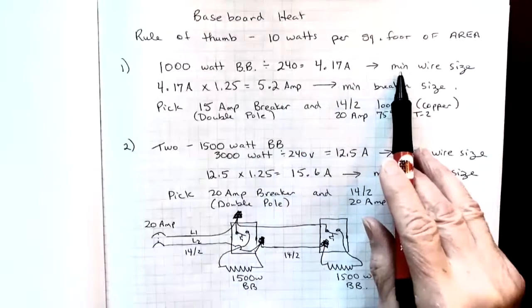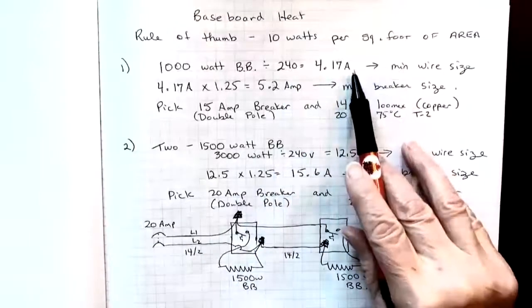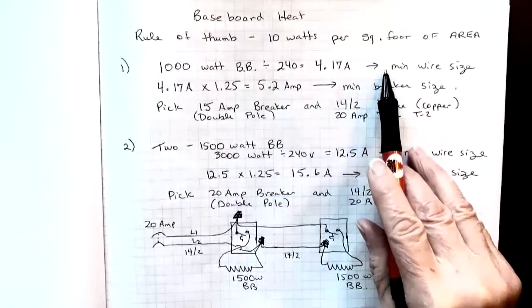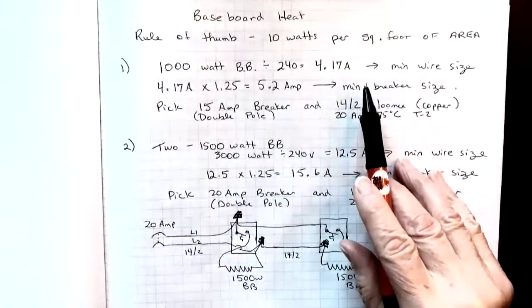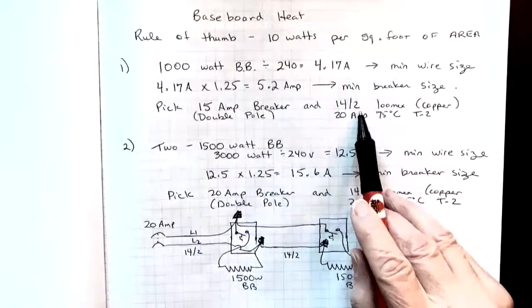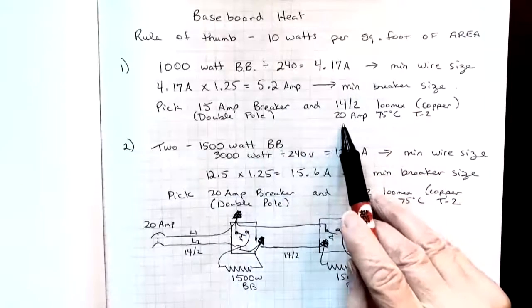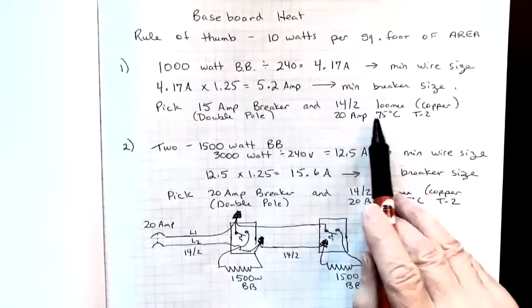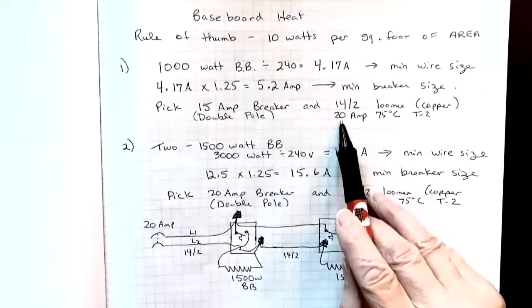So our minimum wire size is going to be based on the 4.17. Of course, we use 14.2 as a minimum wire size. And so we're going to end up with a wire that can easily handle that load. 14/2 Loomex out of table two in the 75 degree column gives us 20 amps.